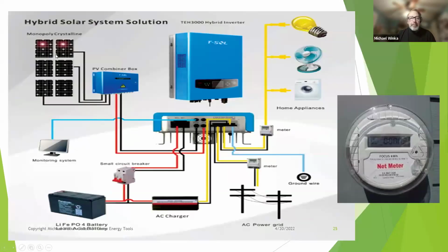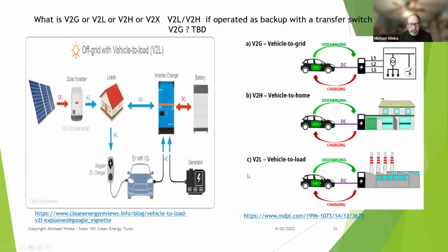Of course, there's always the hybrid system, which combines both. You take your power from the panels through a combiner box to the inverter, which inverts it to AC. You can take that AC, even from the wire line, convert it back into DC through a DC charger, through that charge controller to the batteries, and the batteries send it out as DC, which gets switched to AC back into this inverter and makes it all usable. So that's a hybrid system on top of the AC or DC coupled systems.